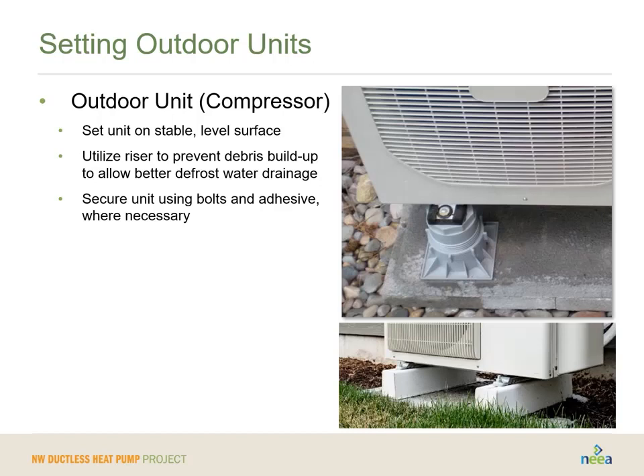The outdoor unit, again, sits on a level surface. That's pretty critical to make sure these things will run correctly. We want to use these risers, as I mentioned before. Here's a different version of it on the top picture. And you definitely want to make sure that you're using both bolts and adhesive to secure this. We want to make sure that this system will not go anywhere.